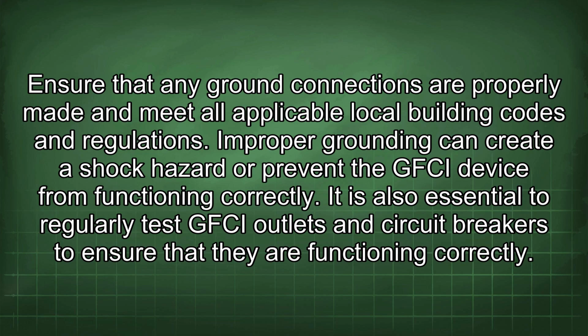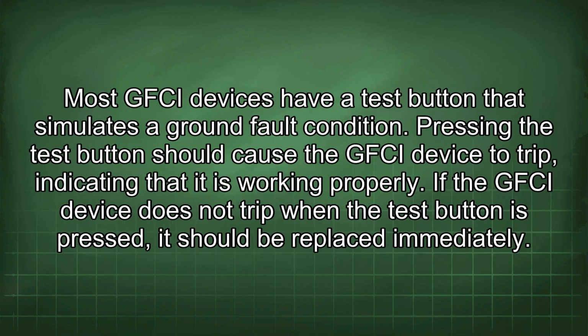It is also essential to regularly test GFCI outlets and circuit breakers to ensure that they are functioning correctly. Most GFCI devices have a test button that simulates a ground fault condition. Pressing the test button should cause the GFCI device to trip, indicating that it is working properly. If the GFCI device does not trip when the test button is pressed, it should be replaced immediately.